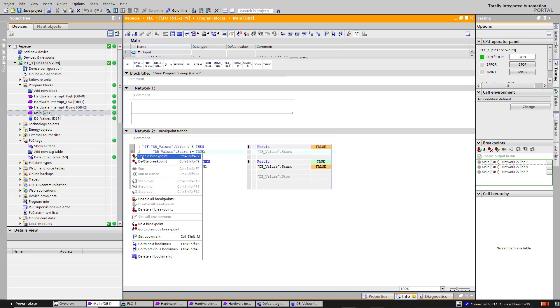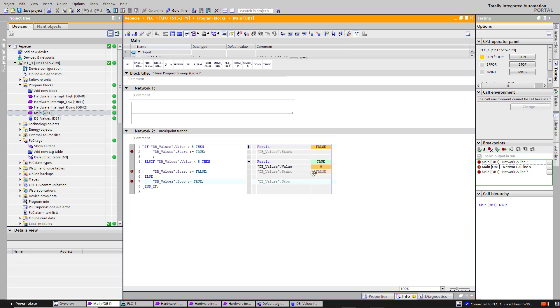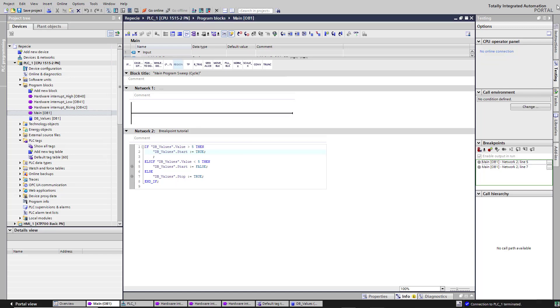Okay, now we can enable our breakpoints. Yes, you can see it's enabled. So now we are here because value equals 0 and this is true — value less than 5. Yes, 0 is less than 5, so Start is false. Now let's change value to 6 and click Run. You can see it jumps here because value is greater than 5, value equals 6, so Start is true. So that was basic breakpoint tutorial in TIA Portal. Thank you for watching.